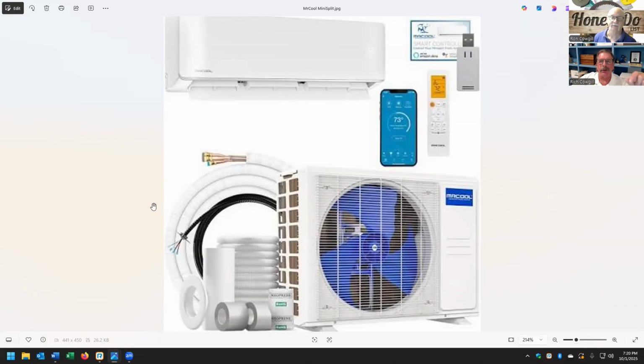36,000 is going to be too big. It will not run long enough. It will hit your set point and turn off, but it will not dehumidify. So you'll be miserable, it can be humid and cool, and you're going to say this thing is no good, but it's because you sized it incorrectly. Don't upsize.